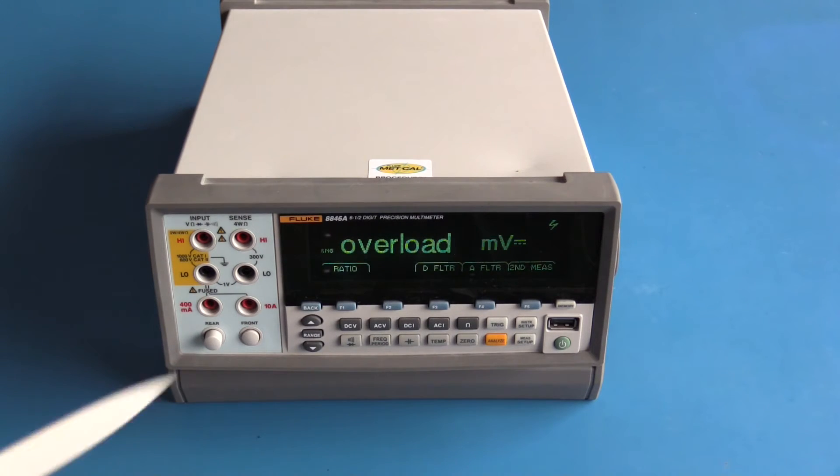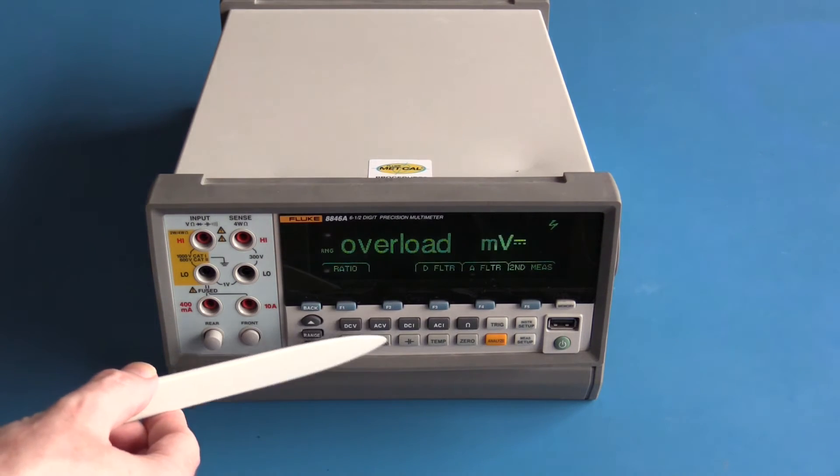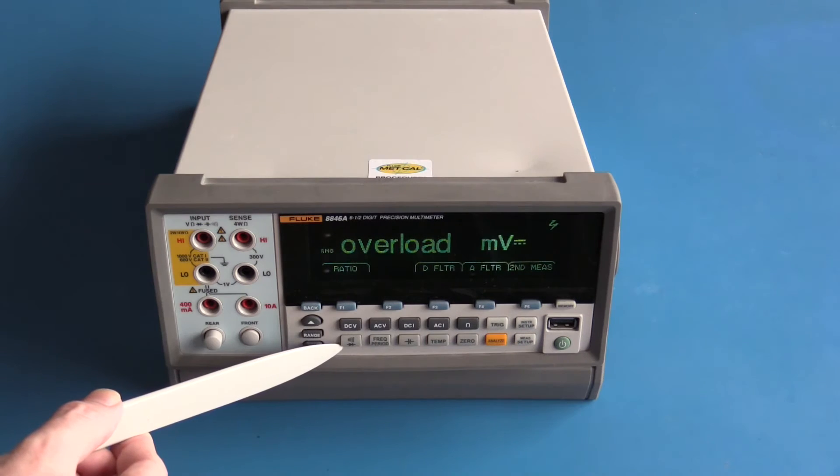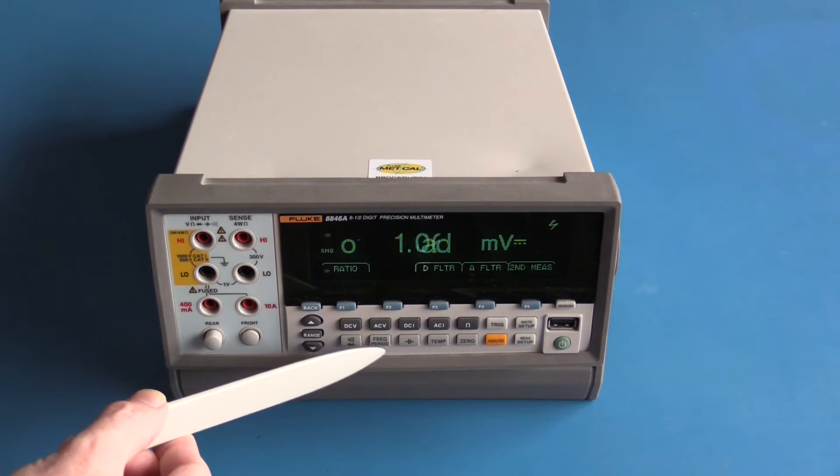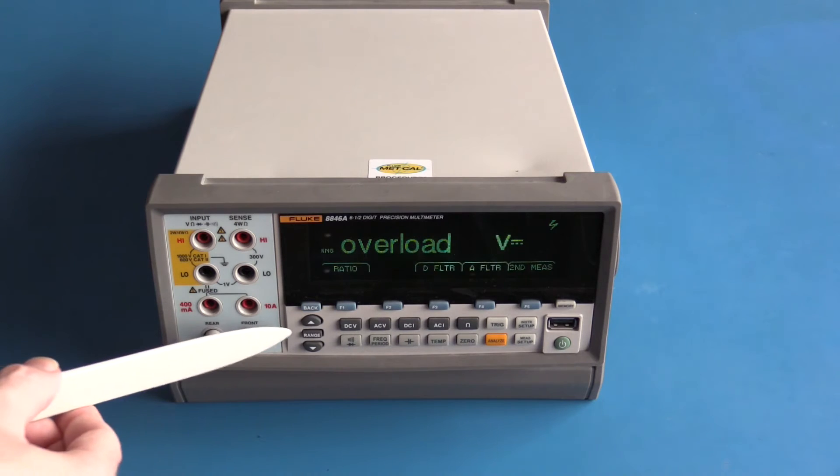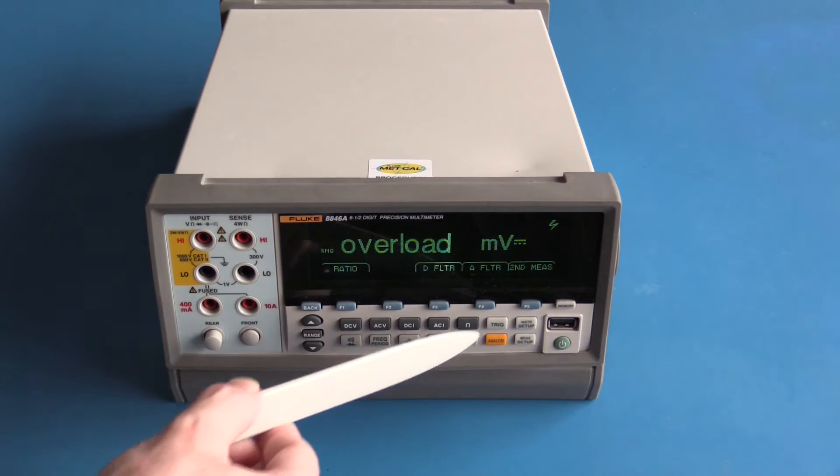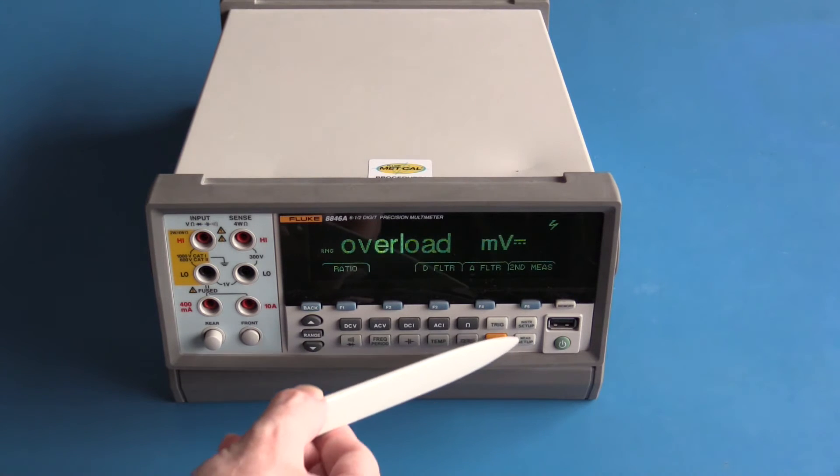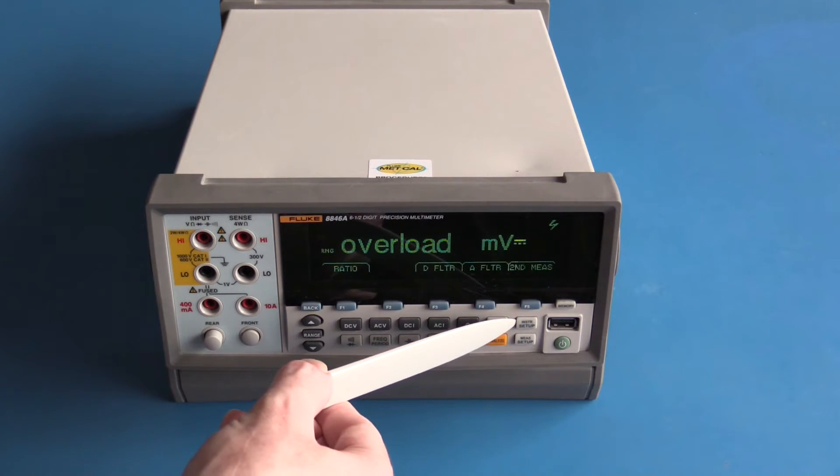This meter has a VFD, it is dot matrix and we have a number of soft buttons underneath the display. Functions on this meter include DC volts, AC volts, DC current, AC current, ohms, continuity and diode, frequency, capacitance, temperature. This meter is auto ranging but you can override that. There is also a trigger function, analyze which we won't really get into today, your measurement setup and the instrument setup.